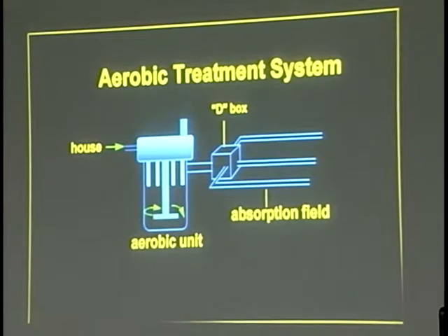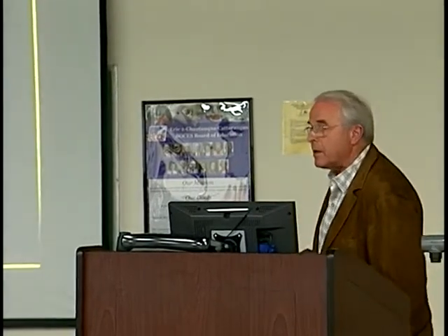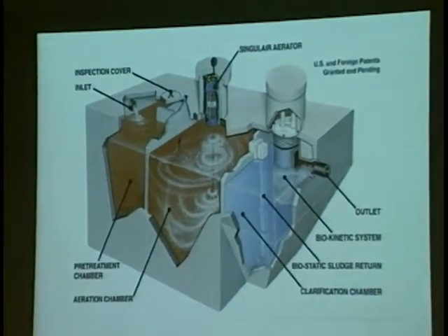What do these units do? When we first started putting them in the mid-80s, they were tested by the National Sanitation Foundation. Those that met the Class I classification have a 90% efficiency rating in removing your disease-causing pathogens and bacteria. What they do not remove are your nutrients such as phosphorus and nitrogen. Phosphorus and nitrogen are the fertilizer, right? Makes plants grow, algae blooms, seaweed growth. The installation of aerobic units is the same way as a septic tank — put them in the ground, put a level on them, make sure they're set level. This is a multi-flow unit; this is a Norweco Singulair unit, larger, more the size of a concrete tank. They have a pretreatment chamber, an aerator here to oxidize and break down your disease-causing pathogens, a sludge return tank, and a filter system before the outlet.